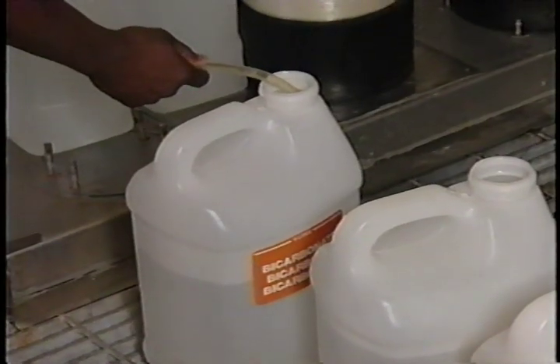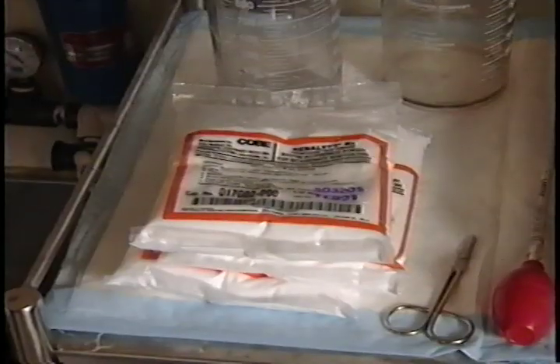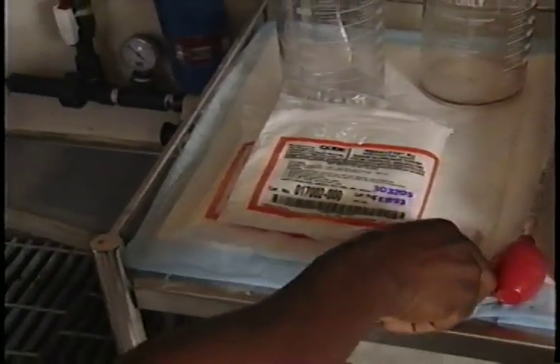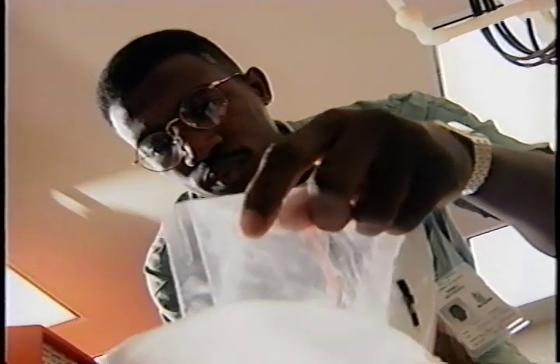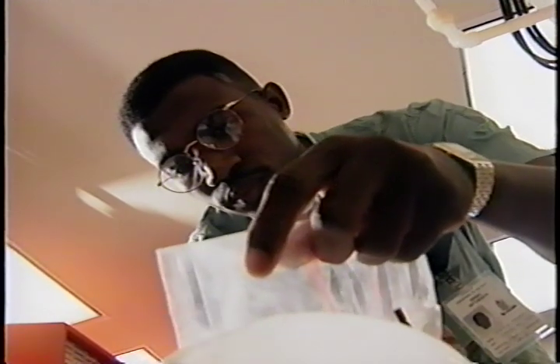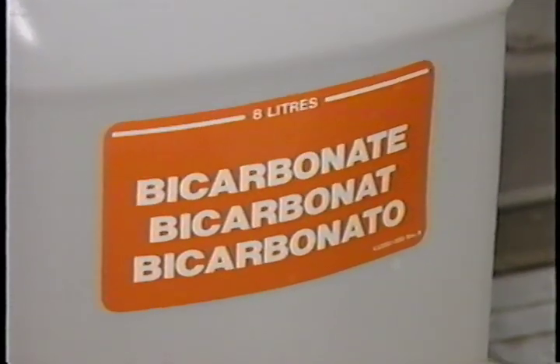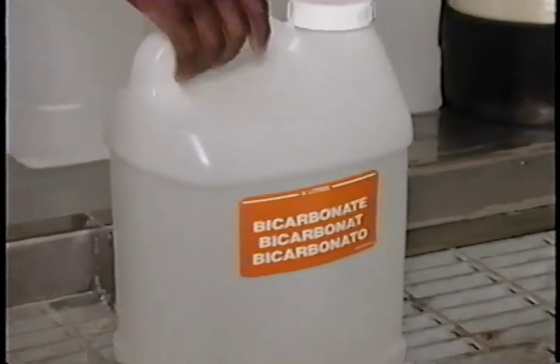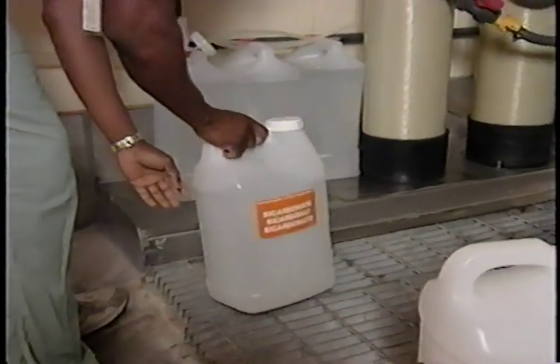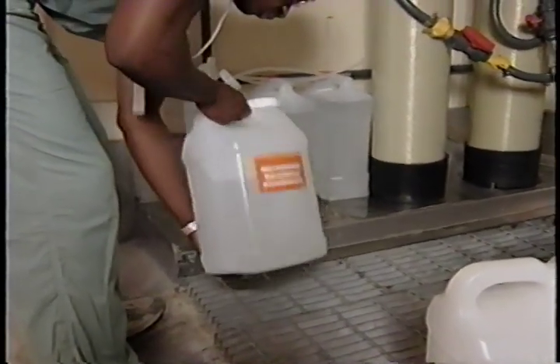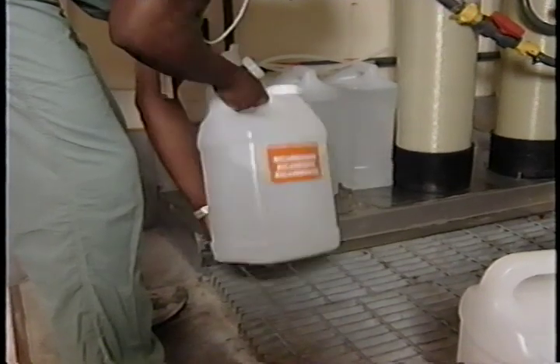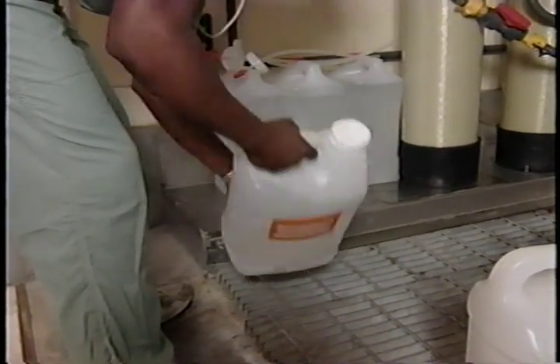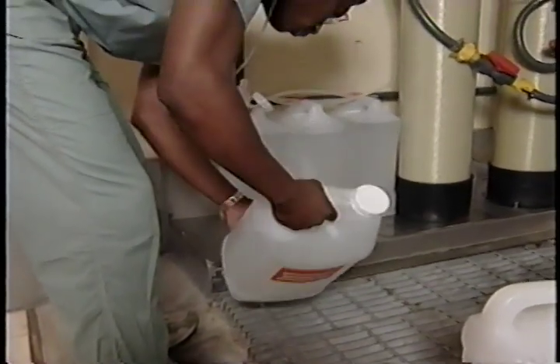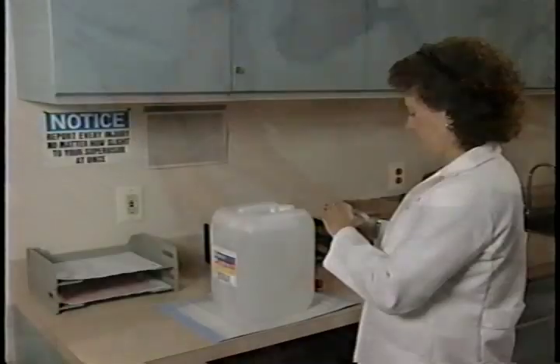Use water that meets the AAMI standard when mixing the powdered sodium bicarbonate into a liquid. The water should be at room temperature for the best mix with the sodium bicarbonate. Never shake the container, as this releases the carbon dioxide. Remember, the mixed bicarbonate dialysate should be discarded after 24 hours because of the risk of potential bacteria growth.